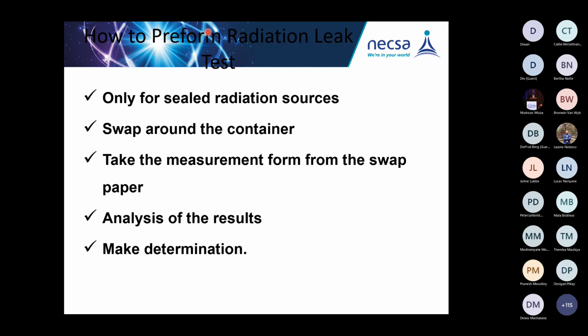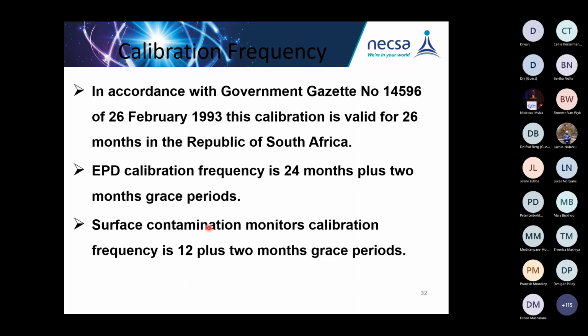How to perform the radiation leak test. Only for a sealed radiation source, you wipe around the container, and then you take the measurement of the swab paper. You use the instrument that I showed you, and analyze and make the determinations. For you to make the determinations, you also need to know the reference levels. And the calibration frequency, this is the Government Gazette number 14596, 26 February 1993. It is so clear that the calibration of the EPD is 24 months plus a two-month grace period, and surface contamination 12 months plus a two-month grace period.